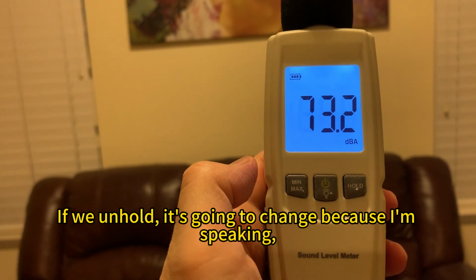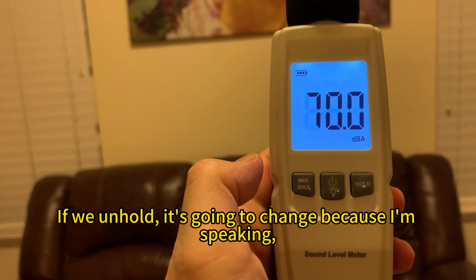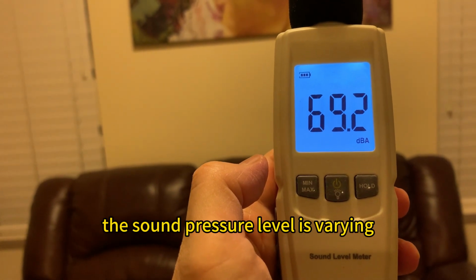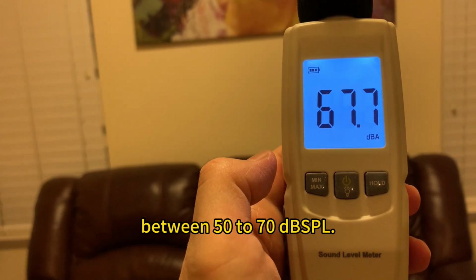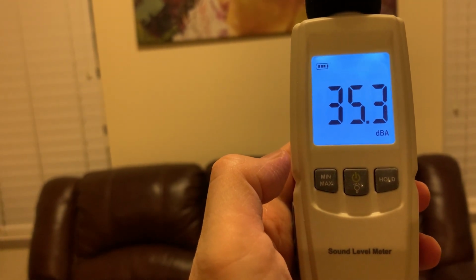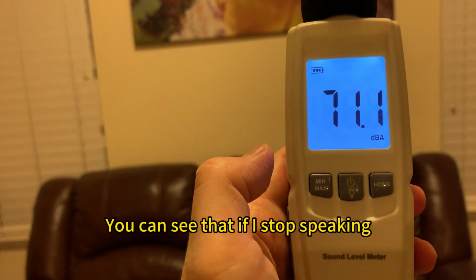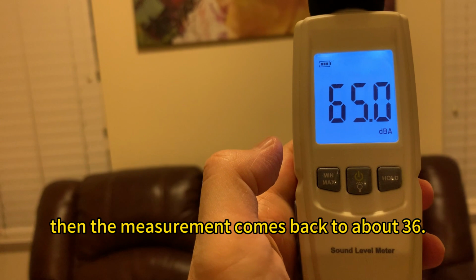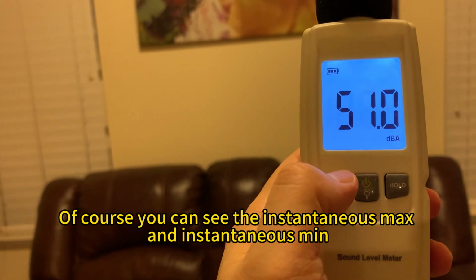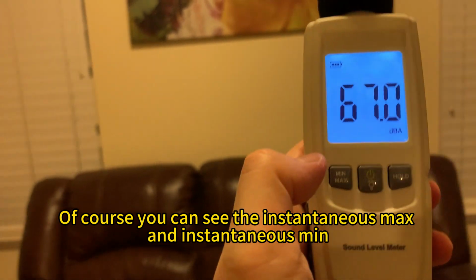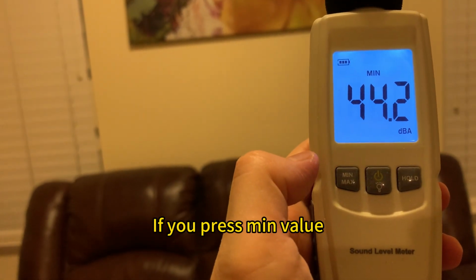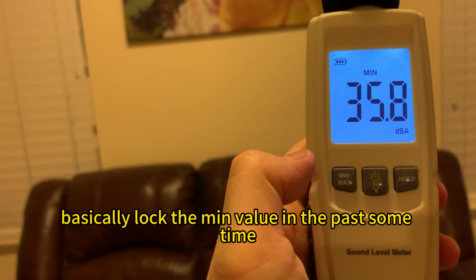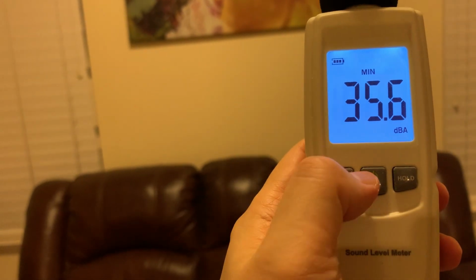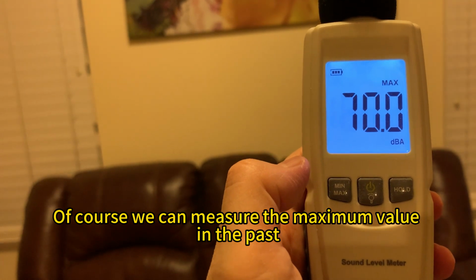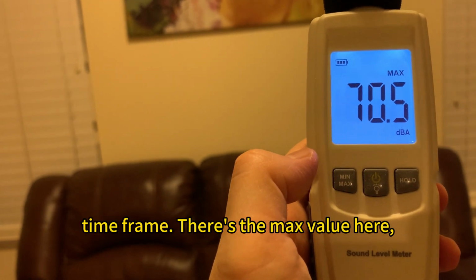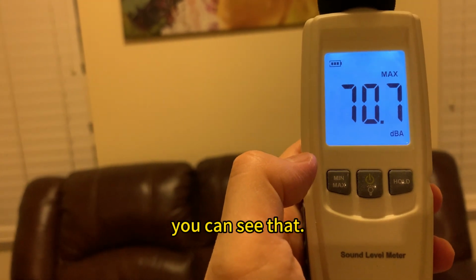If we unhold, it's going to change because I'm speaking. The sound pressure level is varying between 50 to 70. You can see that if I stop speaking, then the measurement comes back to about 36. And of course, we can see the instantaneous max and instantaneous min. If I press min value, it basically locks the min value in the past some time. And of course, we can measure the maximum value in the past time frame. So there's a max value here. You can see that.